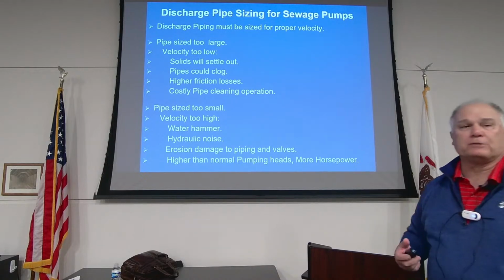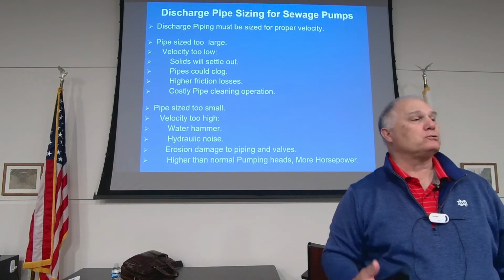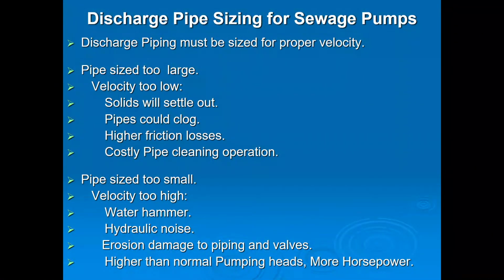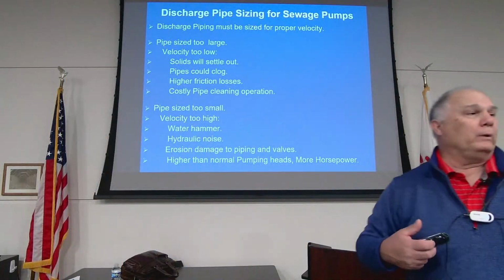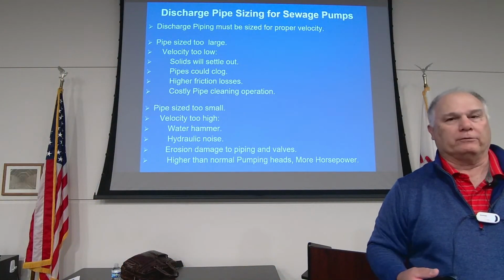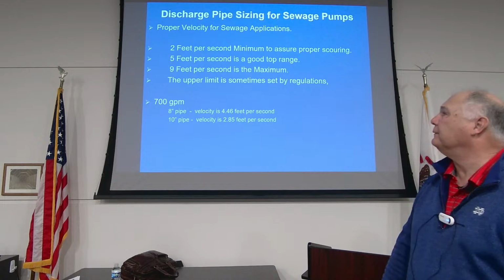So we talk about discharge pipe: we don't want it too big, we don't want it too small. When we talk about too big, what's going to happen? It's going to plug up. It's going to have plenty of capacity, but solids are going to settle out, and eventually we're going to have higher friction losses because crap's settling out. We don't want it too small, because then we get water hammer, we get pipe wearing out, and all those other issues we have to deal with.